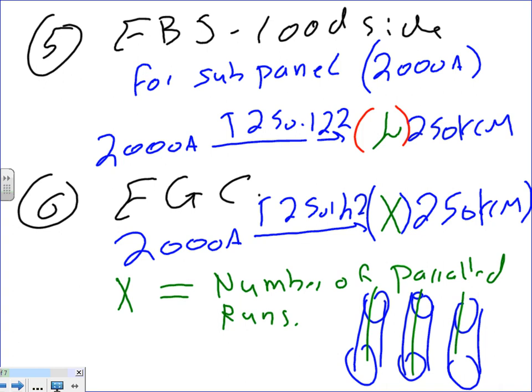Any question, guys, about the equipment grounding conductor and the equipment bonding jumper load side? By the way, why do they call them load side? Because they're on the load side of the service. Everything is by the service. A service disconnect means is here. If I am down here, that's a load side. If I'm up here, that's a line side.